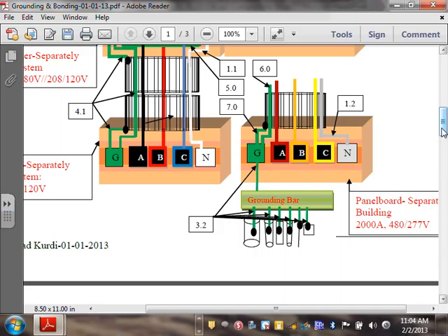If it's EMT, or if it's rigid, or if it's PVC. Except if it's PVC, you must do that. If it's EMT or rigid, you don't have to do that. You can depend on your rigid or EMT as your equipment grounding conductor. And being an engineer, I really don't like to depend on rigid at this amperage, at this voltage, to be my only equipment grounding conductor. So, okay, that's how we size it.